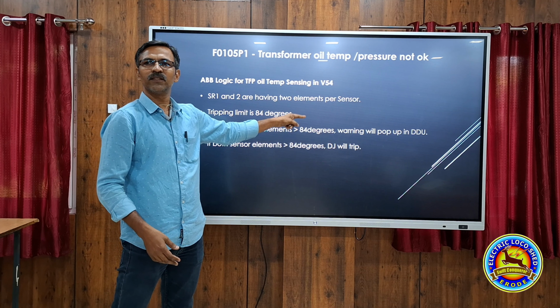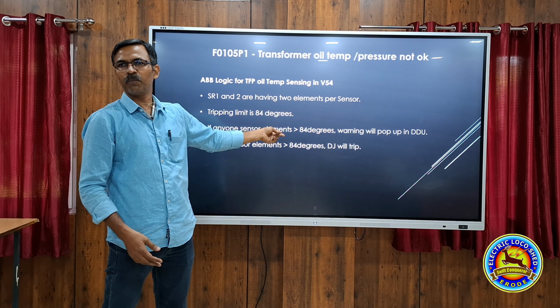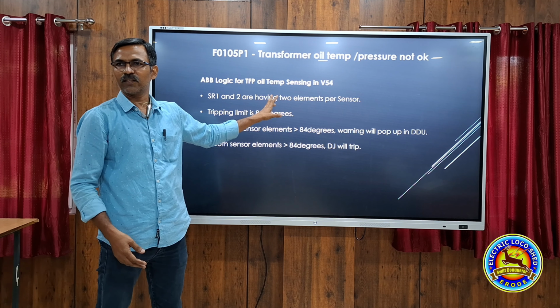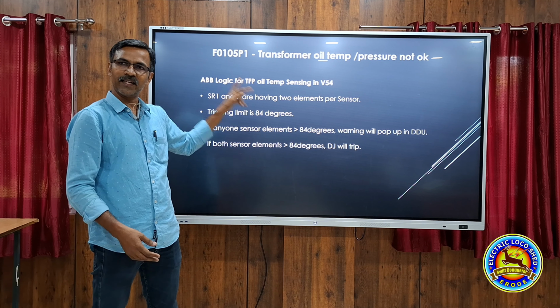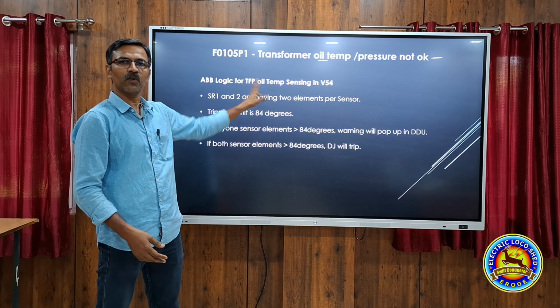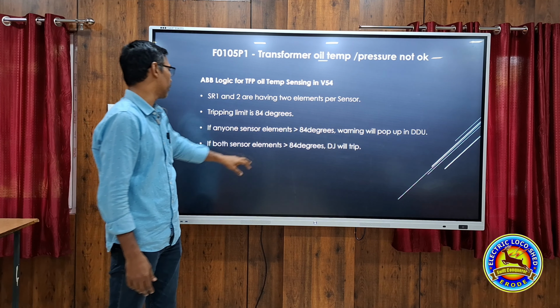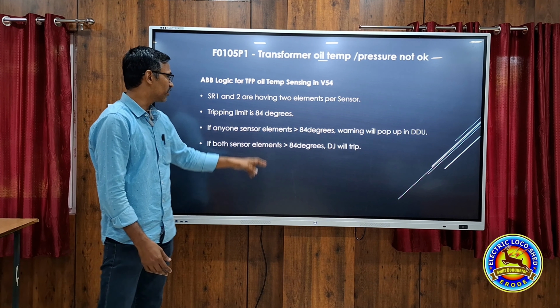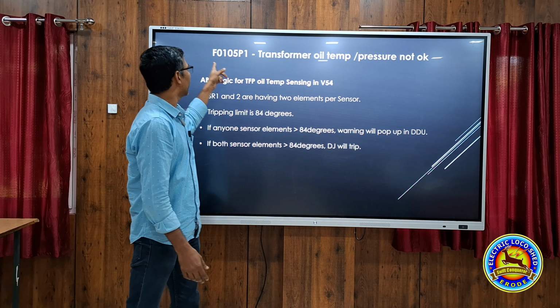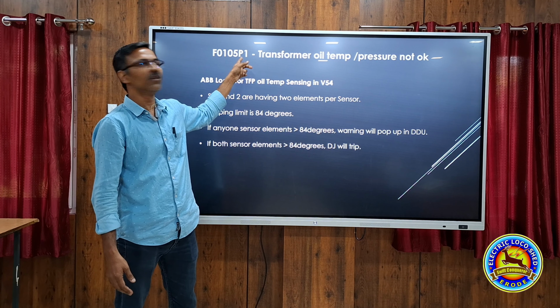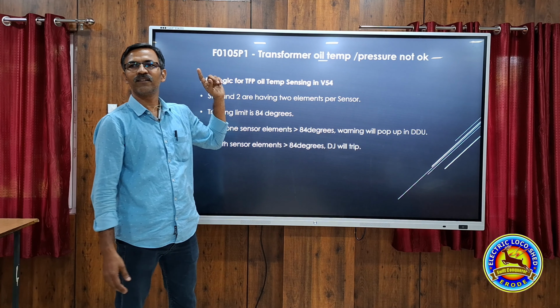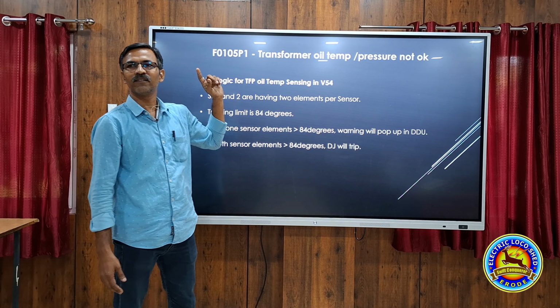If one element crosses 84, it's okay. Only one pop-up will come and the loco will work. If both elements cross 84, then that is the exact issue, and the loco DJ will trip. That's the correct logic. But in that case also, this pop-up will come like this only: F0105 P1. That should be changed. That was discussed in the last FAM.